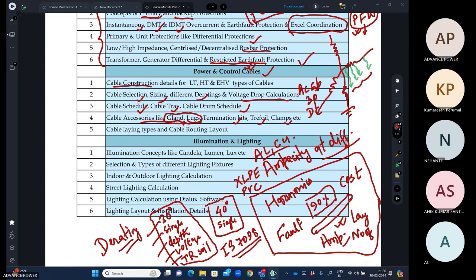In cable, it's not very easy to design. There are so many phenomena. Somewhere people will ask you why you are laying single core cable, why not three core cable. Some will ask why you are using the armor. When you are using the armor, will you connect the armor to ground at the source side, or at the load side, or both sides? Why are we doing the trefoiling? Why are we not laying in a flat condition? What will be the unbalance, and how will that unbalance be taken care of in the cable?